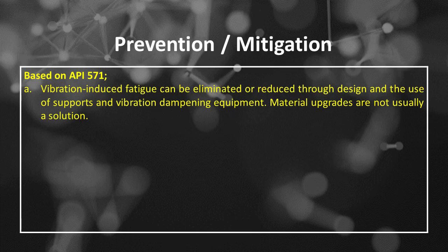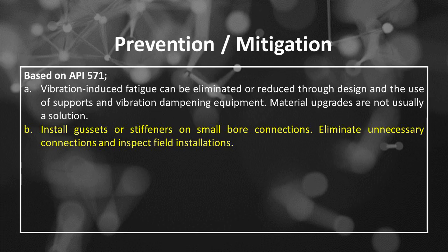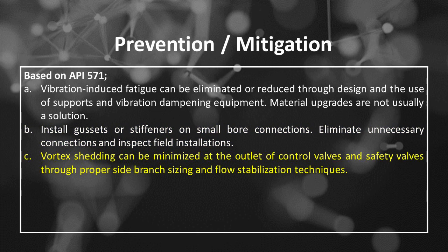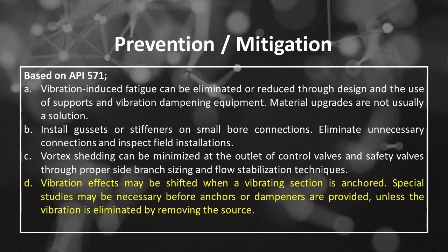The first is vibration-induced fatigue can be eliminated or reduced through design and the use of supports and vibration dampening equipment. Material upgrades are not usually a solution. The second is install gussets or stiffeners on small bore connections. Eliminate unnecessary connections and inspect field installations. The third is vortex shedding can be minimized at the outlet of control valves and safety valves through proper side branch sizing and flow stabilization techniques. The fourth is vibration effects may be shifted when a vibrating section is anchored. Special studies may be necessary before anchors or dampeners are provided, unless the vibration is eliminated by removing the source.